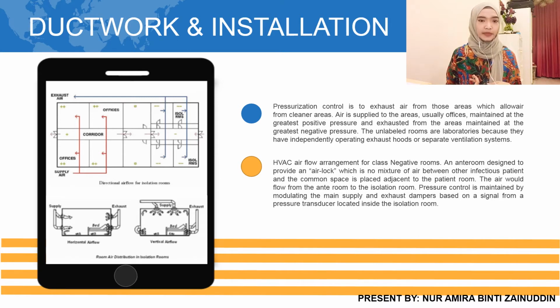Secondly, it shall be maintained at negative pressure, except for the laboratory, because the laboratory has its own exhauster. The third point is that the anteroom is known as an airlock because it prevents the mixing of air between infectious COVID-19 patient areas and other areas.